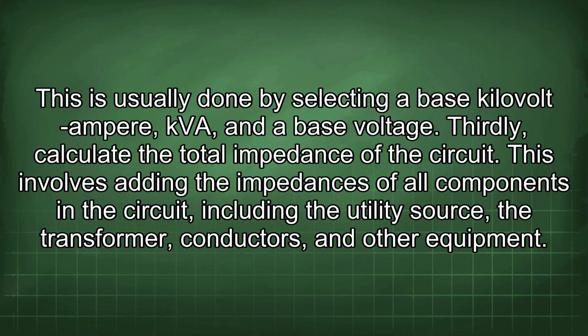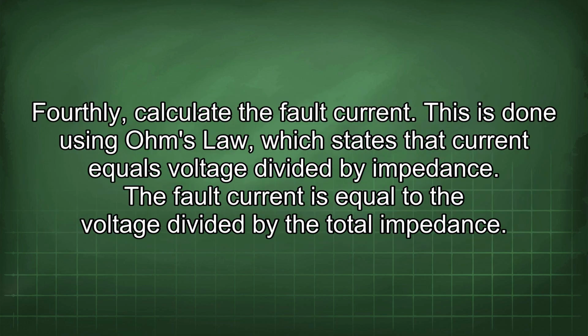Thirdly, calculate the total impedance of the circuit. This involves adding the impedances of all components in the circuit, including the utility source, the transformer, conductors, and other equipment. Fourthly, calculate the fault current. This is done using Ohm's law, which states that current equals voltage divided by impedance. The fault current is equal to the voltage divided by the total impedance.